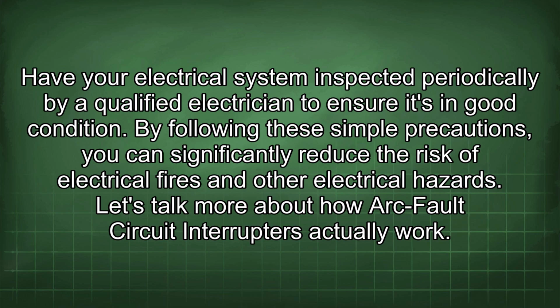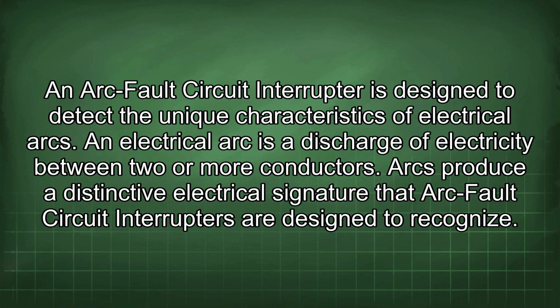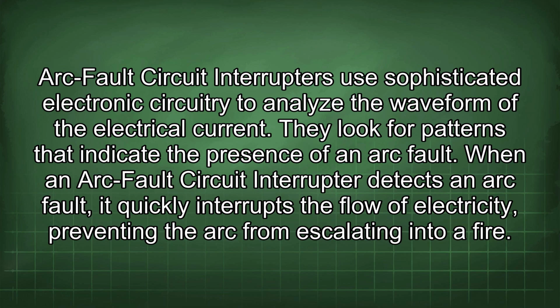Let's talk more about how arc fault circuit interrupters actually work. An arc fault circuit interrupter is designed to detect the unique characteristics of electrical arcs. An electrical arc is a discharge of electricity between two or more conductors. Arcs produce a distinctive electrical signature that arc fault circuit interrupters are designed to recognize. They use sophisticated electronic circuitry to analyze the waveform of the electrical current. They look for patterns that indicate the presence of an arc fault. When an arc fault circuit interrupter detects an arc fault, it quickly interrupts the flow of electricity, preventing the arc from escalating into a fire.